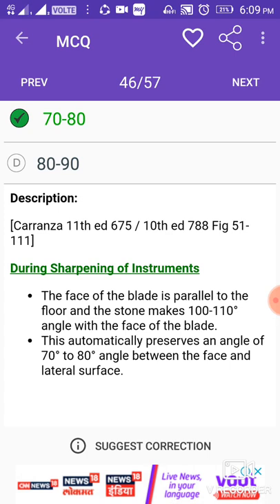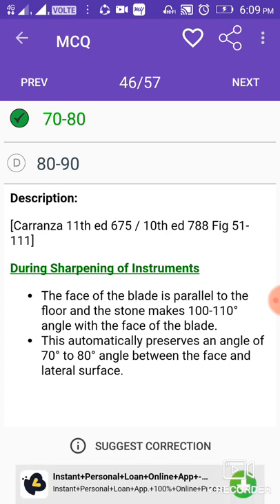During sharpening of instruments, the face of the blade is parallel to the floor and the stone makes a 100 to 110 degree angle with the face of the blade. This automatically preserves an angle of 70 to 80 degrees between the face and lateral surface.